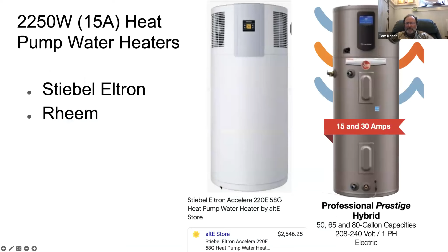151,000. And then I just assumed that the peak day of the month would be 3 times the average because we get these cold snaps. So that'd be 450,000 BTUs that we need to deliver from the heat pump. And assuming that we just wanted it to run 16 hours at its rated level, because heat pumps like to run nice long hours and just keep going at a moderate pace. And so that told me how many BTUs per hour were needed, and it's 28,000 in that row right below. Dividing by 12,000 BTUs in a ton, it came up to just under 2.5 tons in that bottom row.